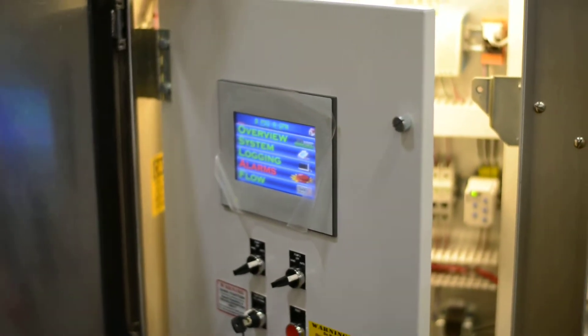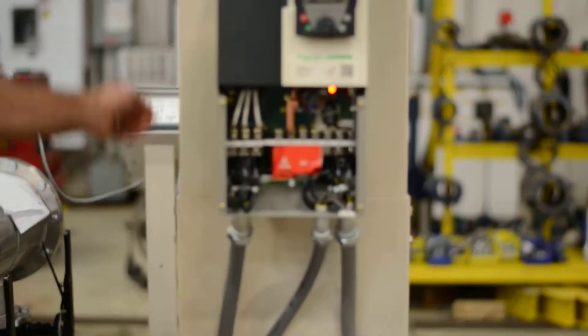Just check to make sure nothing's falling apart on this stuff, and then go over to the other side on the mechanical side. Do the same thing—go through, look for bolts, do your tug tests on here, on your filter, anything on the covers. Make sure everything is good.